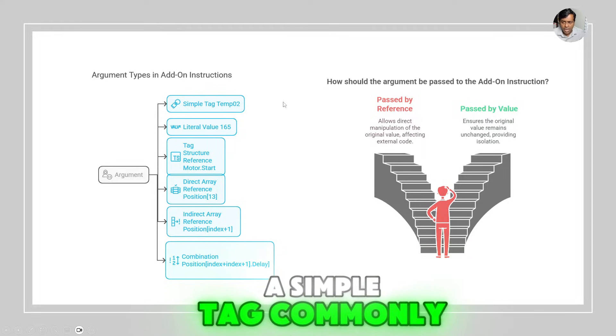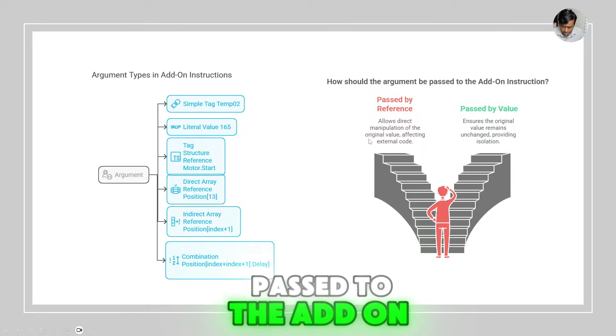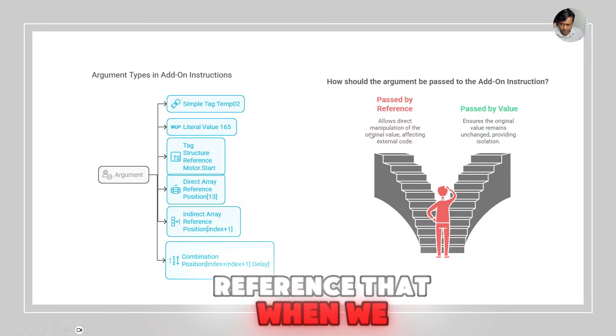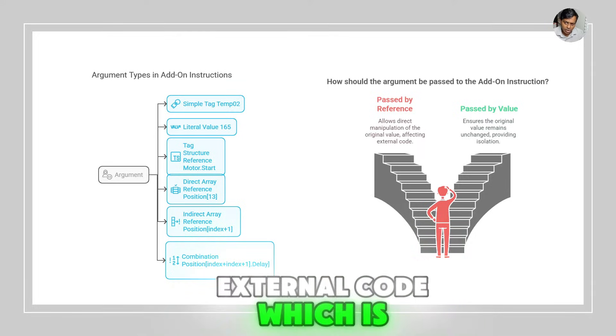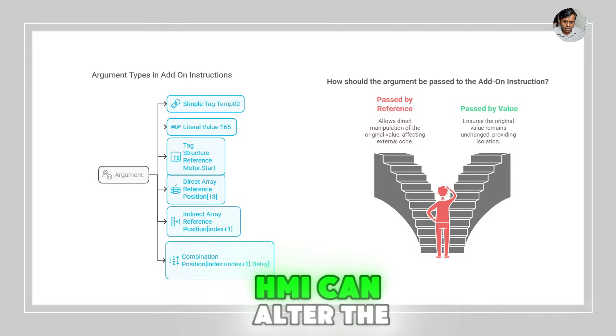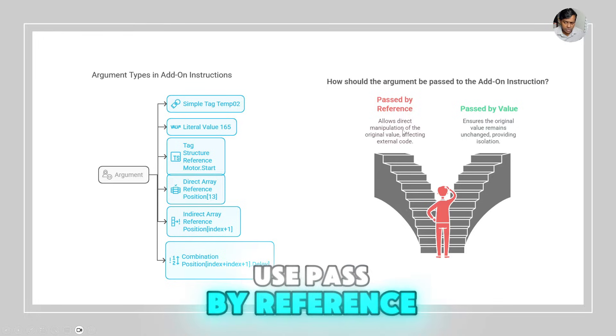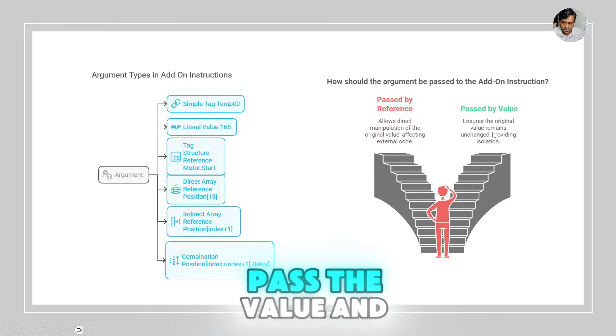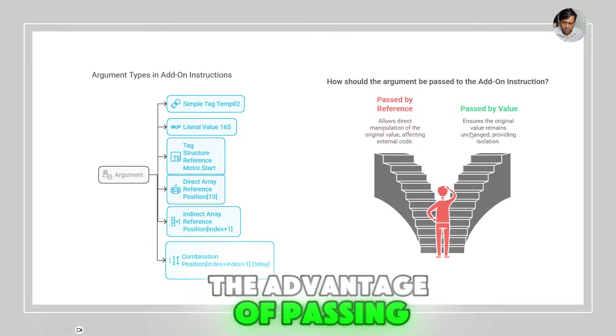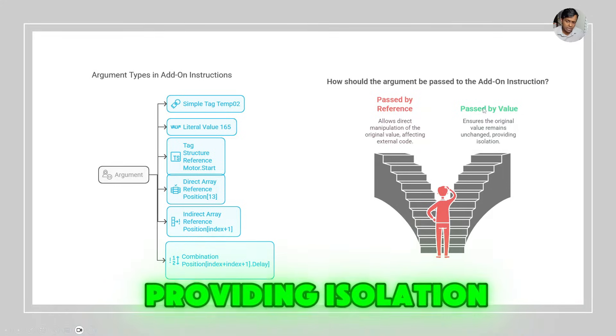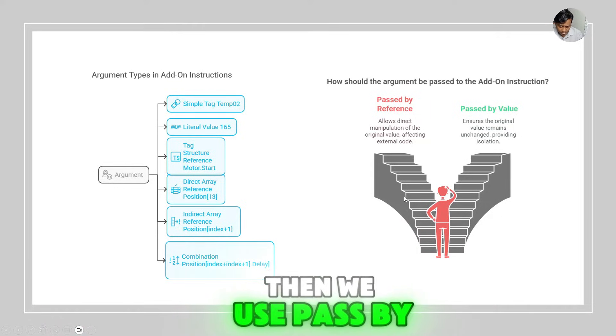Typically we use a simple tag. Now, arguments can be passed to an add-on instruction set by reference or by value. Passing by reference means the tag is available for external code — such as an HMI — to change, even before the AOI uses it, so you need to be careful. Passing by value means you just pass the value and the AOI acts on it. The advantage of pass by value is that the original value remains unchanged, providing isolation. If you don't want anyone else to change the value, use pass by value; otherwise use pass by reference.